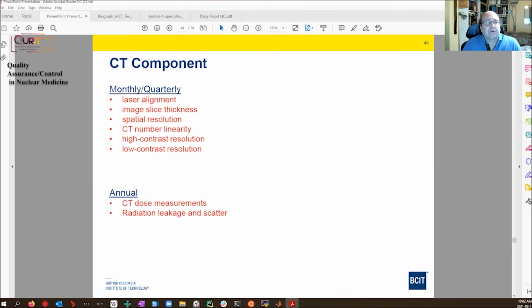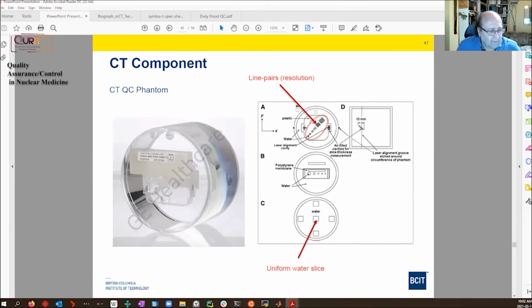And then annual tests. These more stringent tests usually involve a very complicated CT phantom, which has various components. It's got sections where you would measure uniformity. It's got line pair sections of the phantom, which are used for assessing resolution.